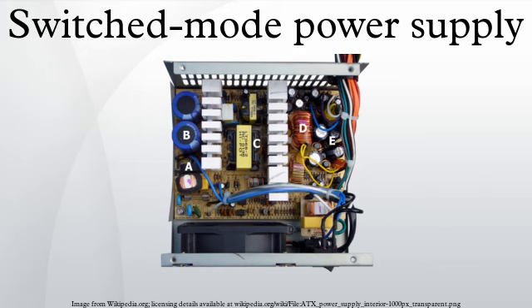The rectifier produces an unregulated DC voltage which is then sent to a large filter capacitor. The current drawn from the main supply by this rectifier circuit occurs in short pulses around the AC voltage peaks. These pulses have significant high-frequency energy which reduces the power factor. To correct for this, many newer SMPS will use a special PFC circuit to make the input current follow the sinusoidal shape of the AC input voltage, correcting the power factor.